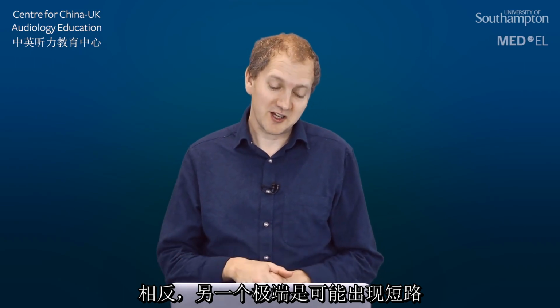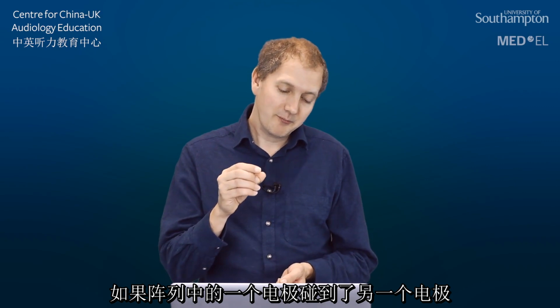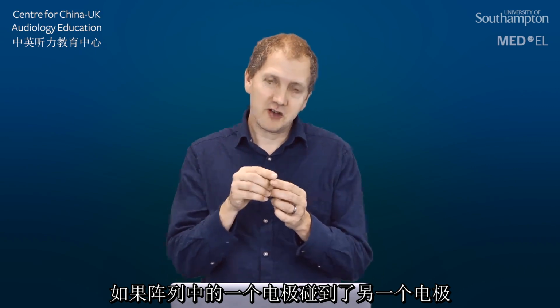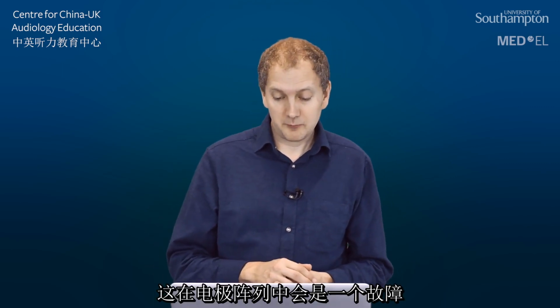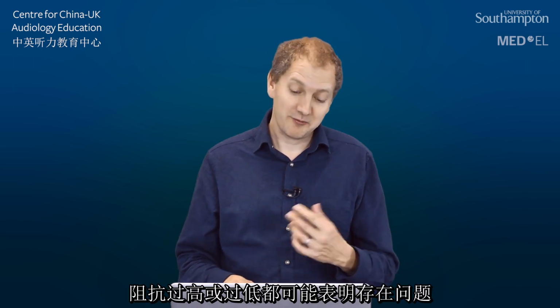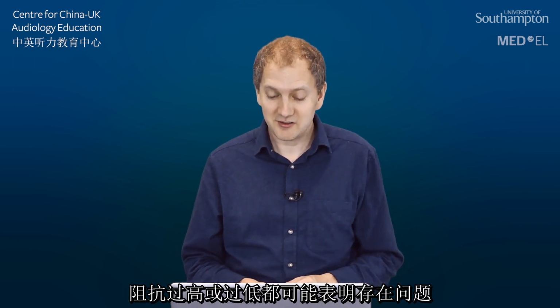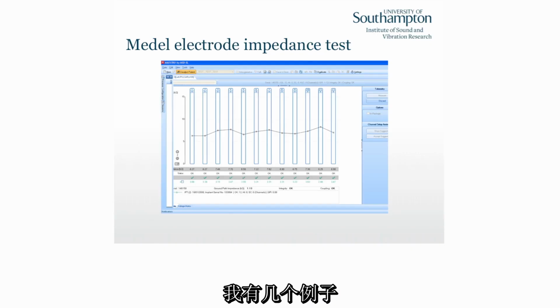Another thing that we might see is the opposite, which is a short circuit. So if one electrode in the array has actually touched another electrode, then we'd get a very low impedance. So that would be a fault in the electrode array, and it might be that we need to turn off certain electrodes because of that. So both a very high impedance or a very low impedance can indicate a problem. And I've got a couple of examples.